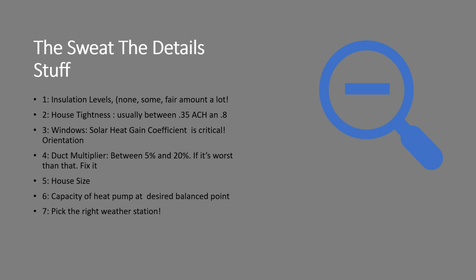Duct multiplier, typically between 5 and 20%. If it's worse than that, you really should fix it. It's hard to make people comfortable with heat pumps with leaky, uninsulated ducts. And insulation is just as important on that ductwork as making sure the air doesn't leak out of it. House size is often important, but as we said, R values and U values and ACH and duct leakage probably have a bigger role, but obviously the larger house, all the other things being equal, will require a larger system.